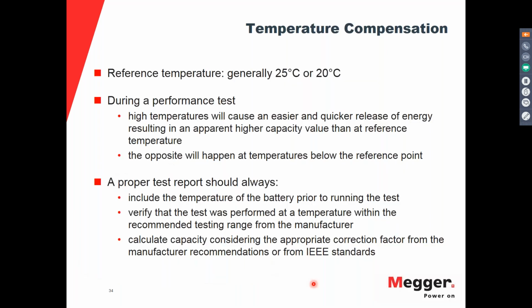Also, when you're running the test, you need to consider the temperature. Remember that batteries are specified for a certain temperature, usually 25 degrees C. I've also seen batteries specified at 20 degrees C. Whatever it is, you should always get your temperature before running the test. At the beginning of the test, you should know the temperature of the battery, not of the room, and that should be used for the correction of the result. When you are reviewing the results, you should always look for that temperature of the battery, and confirm that the result was corrected for that temperature.